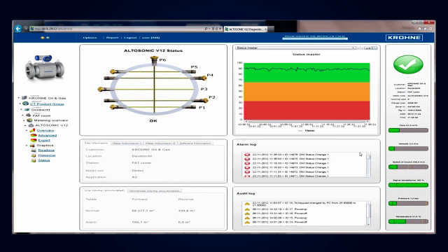One thing you see here, that the flow profile distortion is quite high, it's at 26. It's just below 33. There is no reason for warning. You saw the setup, the meter is running atmospheric air, no inlet and outlet. So the flow profile isn't optimal. Once in a while it slightly goes up and we see a flow profile warning. Again, here you see the meter at this moment is running okay.